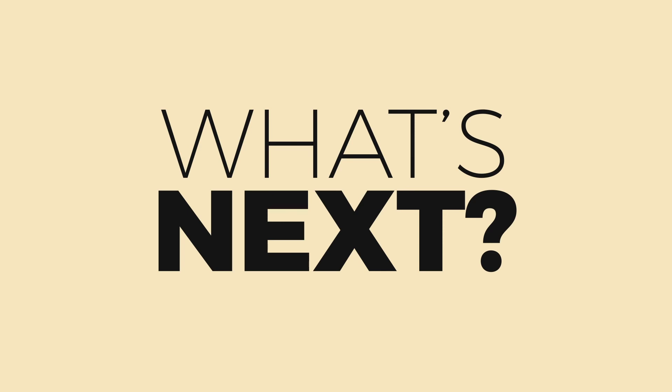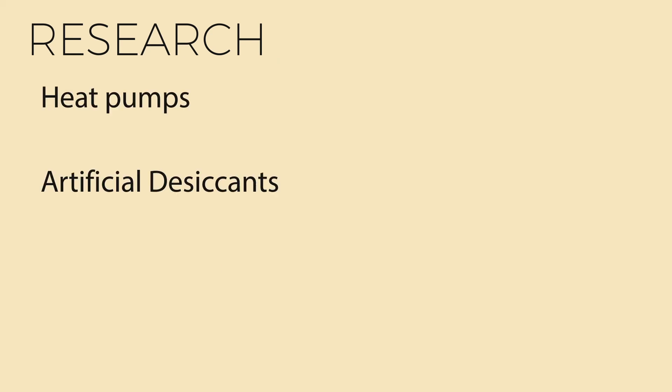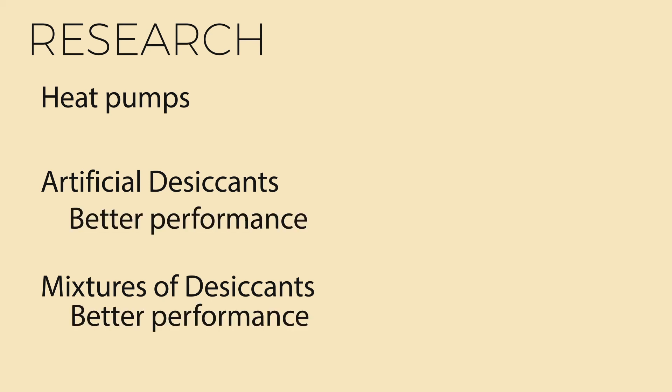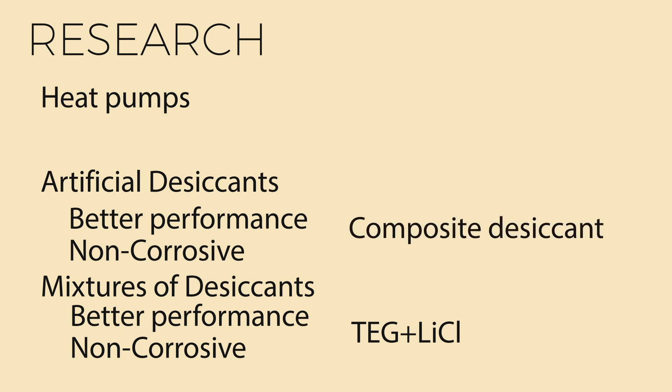So where is this technology going and how does it compare to its alternatives? Recently, researchers have started incorporating heat pumps to transfer heat from the dehumidifier to the regenerator, achieving very high coefficients of performance. Extensive research is focused on developing artificial desiccants and mixtures of different desiccants that have better dehumidification capability and are non-corrosive to equipment such as pumps and heat exchangers used in the system. Triethylene glycol mixed with lithium chloride and calcium chloride significantly increases performance but doesn't solve the problem of corrosion. However, a composite desiccant developed by confining salts to porous adsorbents improves performance, reduces size, and bypasses the corrosive equipment altogether.